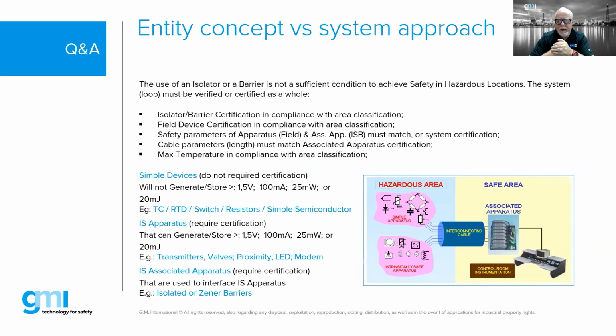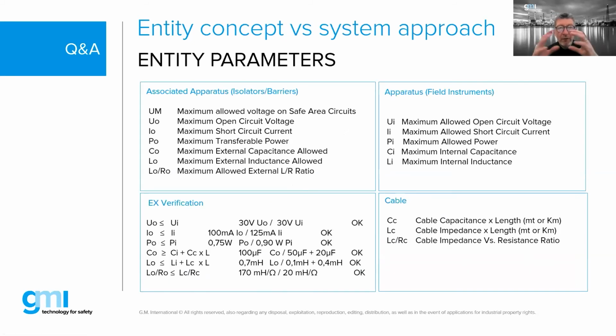Here is an example of the parameter mesh. Basically, the associated apparatus has to guarantee that the maximum voltage, current, and energy we transfer is below what's acceptable. It's about how the device in the field has been certified, because you go into certification and say, I want to certify this at 30 volts, so they check everything at 30 volts. You can say, I want to test it at 20 volts, and then they certify 20 volts. Whatever is selected, there's some reasoning behind it, and then you have to guarantee you stay below that voltage, because otherwise you don't know what's going to happen. Maybe it's still safe, but it hasn't been tested and certified.